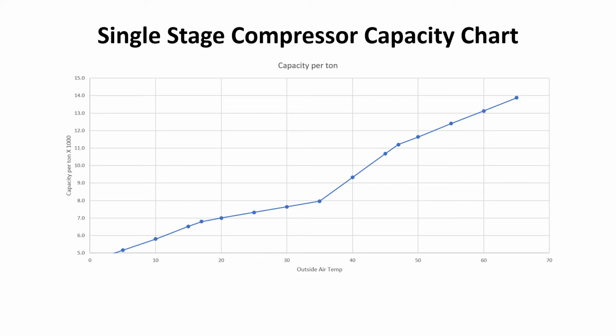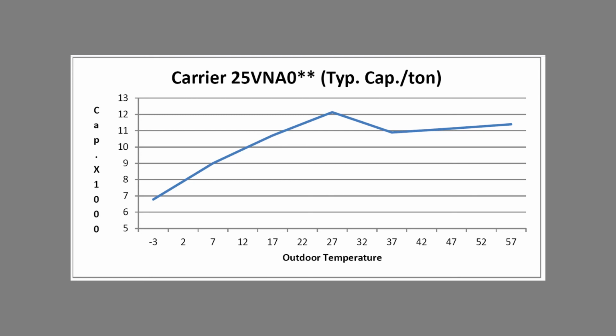And as we go down, we hit what's called the defrost knee, if you will, because at this temperature, you can make a lot of ice, and there's generally a dip in the capacity. But in general, the colder it is, the less capacity the heat pump has. Yes, we now have some extended capacity heat pumps whose curves look very different. Notice that the peak capacity on this system is at 27 degrees. It's actually higher there than it is when it's 52 degrees.